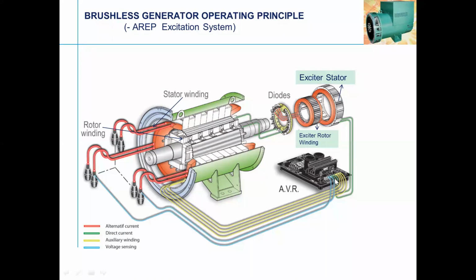It is so advantage, as I was mentioning for PMG, there is a different source of supply giving to the brain, again the AVR. So this is going to decide how much I have to feed to have the system, that means voltage, to the requirement of the load, or you have to have the voltage, current, and power factor. So this brain AVR decides how much I have to pump the excitation to the system, which we'll be discussing. So this is overall, if you can see, AREP and PMG does the same one when we put it on the operational. As an experience of 30 years in this field, I look at this is also a fantastic design from the designers, appreciate for that.